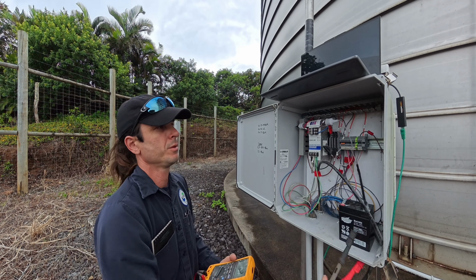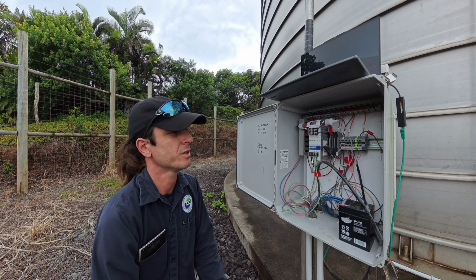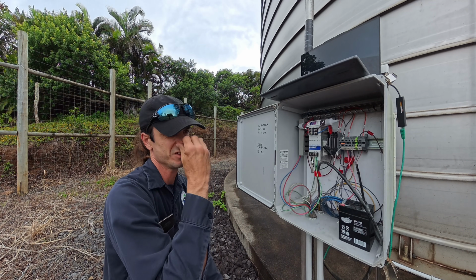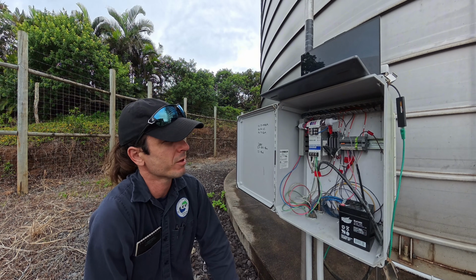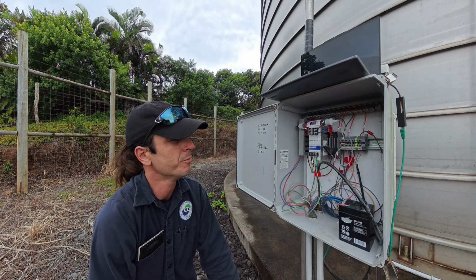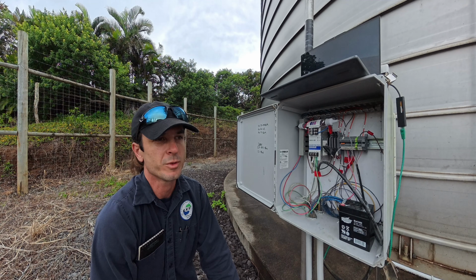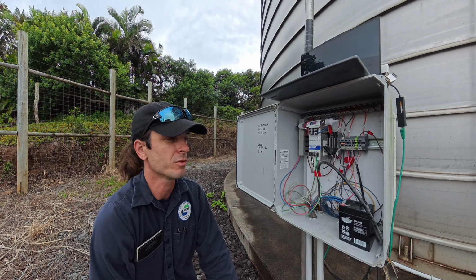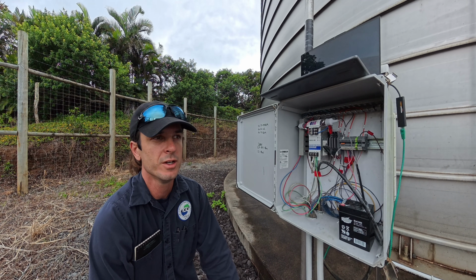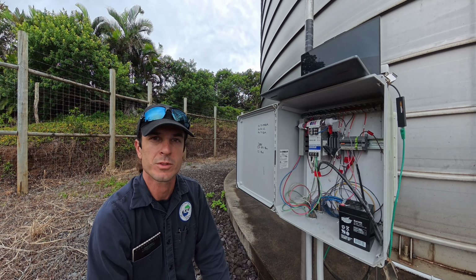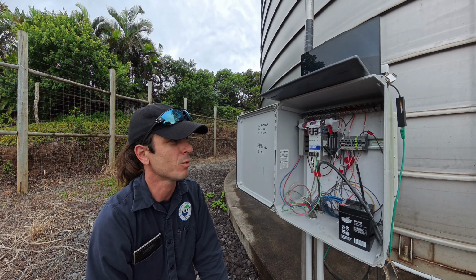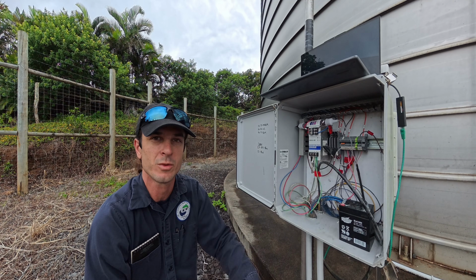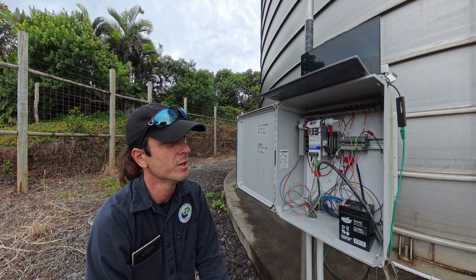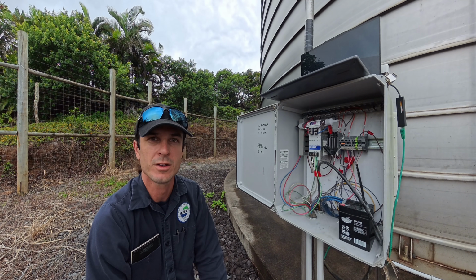Alright, so we got the transducer working again. I disconnected the shield so we don't get into that overcurrent scenario again. And then I'm just going to recommend to the customer that they be aware that the transducer is likely going to fail in the near future. Yeah, so we'll just make that recommendation, and who knows, it could last a while like this. The signal is stable even with the shield disconnected, so I'm not too worried about that. And yeah, we'll see how it goes.